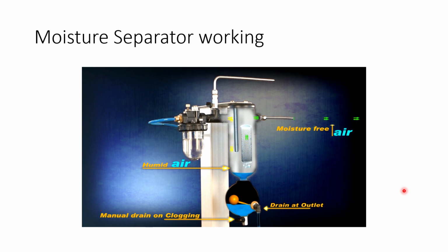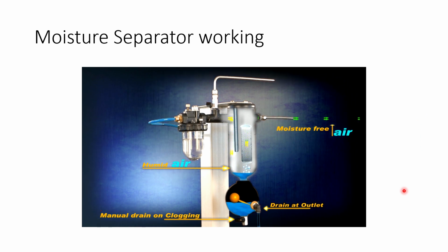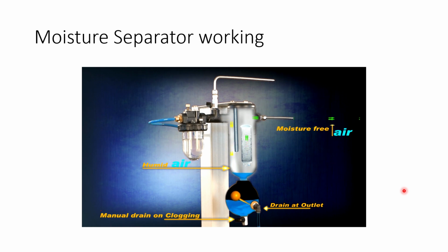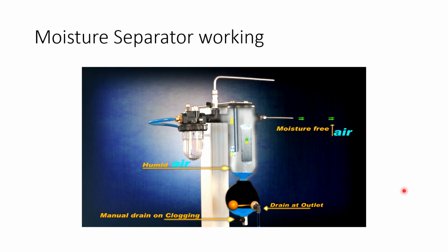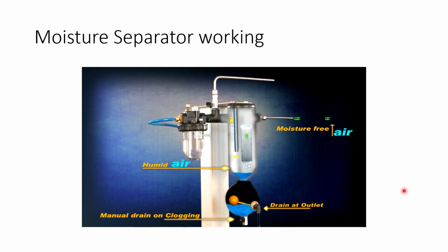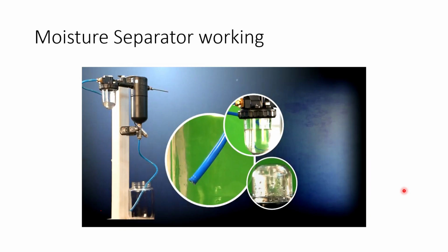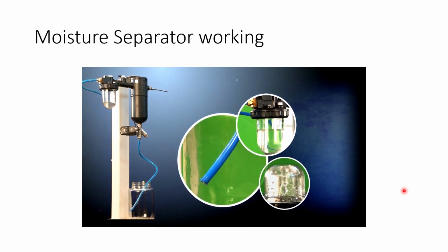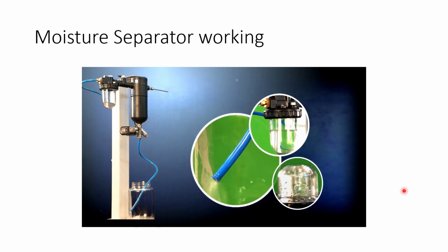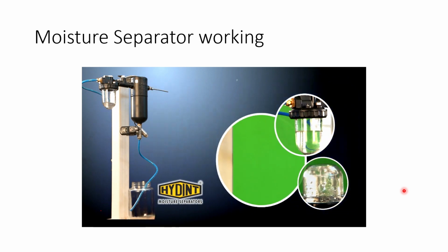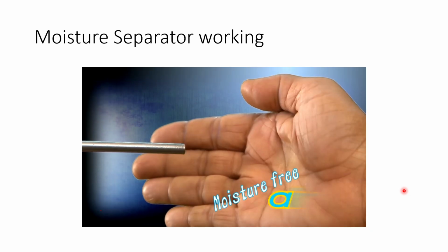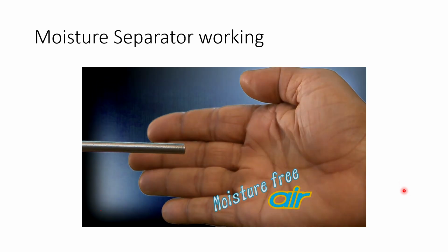as a separator itself. After the air has been relieved of some of its moisture by the baffle, it is subject to another relieving mechanism, the coalescer. See, this is how this coalescer operates. The moisture has a tendency to be attracted to the solid stainless steel due to adhesive forces. Any gathering of water will form a drop, which increases in size and eventually becomes heavy enough to drop downwards to be collected and disposed of. Now, fresh air is there in the outlet.